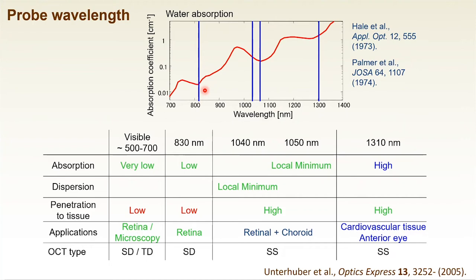The main absorber of the eye — the vitreous, aqueous humor — is essentially water, so water is nominally the only absorber in the eye optics. Light must pass through approximately five centimeters of water before imaging the retina. Therefore, we need to minimize water absorption. The selection of 830 nanometers minimizes water absorption, enabling light to reach the retina.